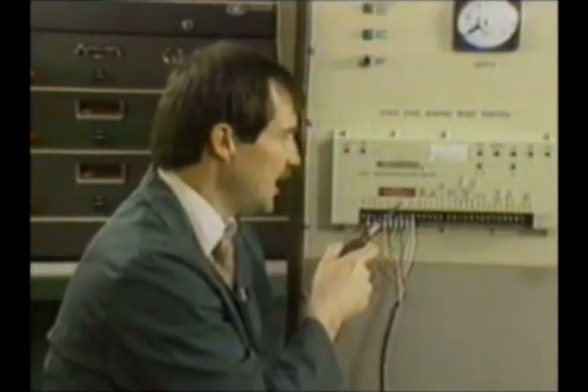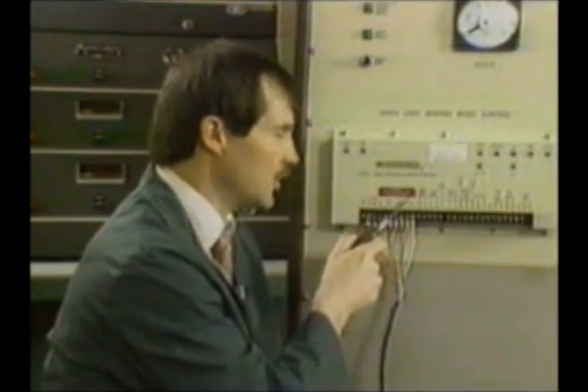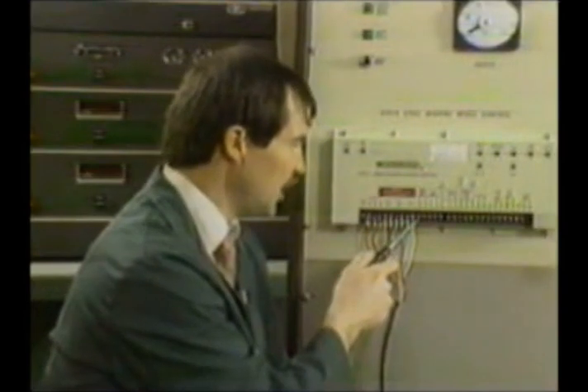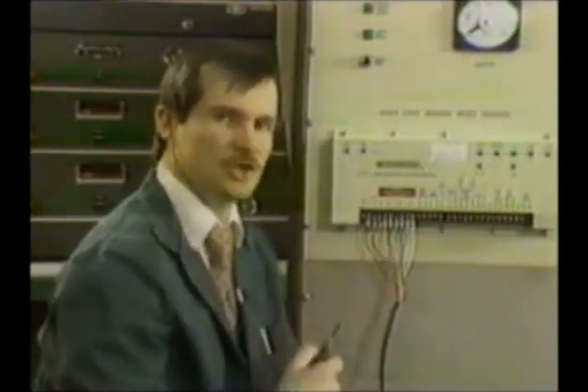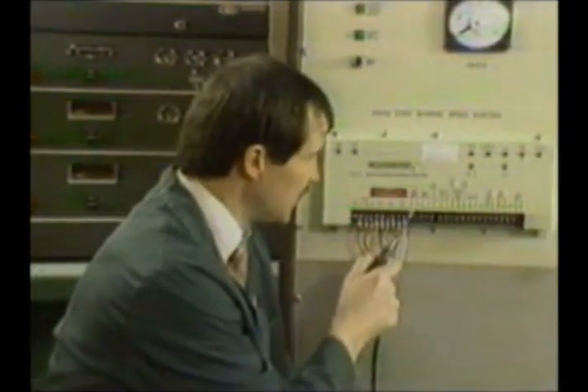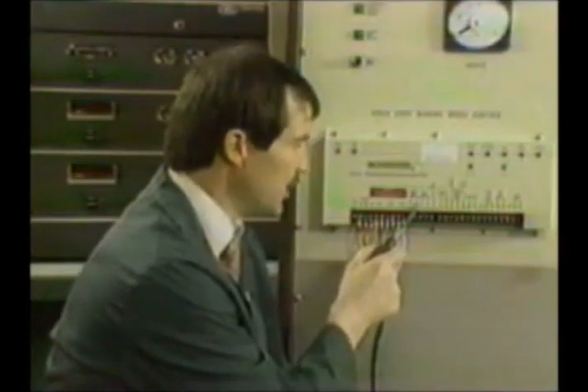the 2301A provides a relay inside the control which will now allow you to hook a 2301A load sharing lines directly up to another 2301A load sharing lines. And the shields can be hooked to both also. Now if you're going from a 2301A control to some other type of electronic speed control, do not continuously run the shield to the next control. Our shields are shown on here for our shielded pairs where they should be connected and if they should be.